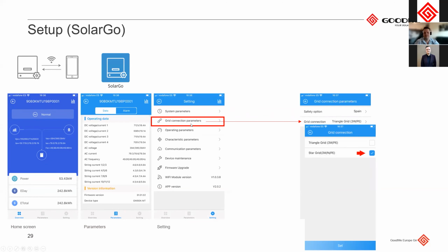Then we just need to go to our grid connection parameters. So there's two selections here that we have to make. We have to select the safety option, which is our country code. So we will select Africa or South Africa if we're installing it in South Africa. I know SolarGo very often doesn't have South Africa. It only has Africa as a selection, but that Africa is NRS. Then based on how you're installing your inverter, if you are installing a device without neutral, make sure you select the device without neutral. If you are installing it with neutral, make sure you select the star grid with neutral. If you do not select this correctly, your device may not synchronize with the grid. So just make sure that this is selected.